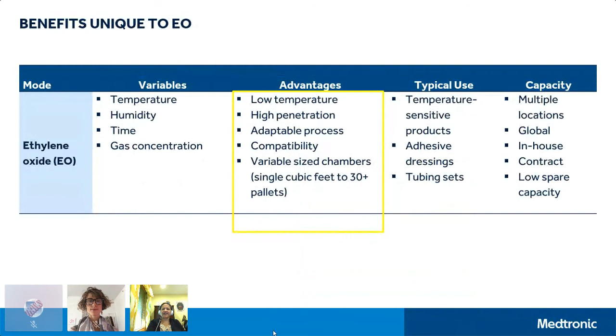One of the things I would like to point out here is a typical sterilization process profile that describes the mechanism of how EO is working. The first step is the preconditioning phase, where you require the load to be brought up to a specific temperature and humidity level. And these are very essential for proper sterilization. The important thing to note here is the humidity requirements. A 30 to 80% humidity range is preferred for optimum sterilization effectiveness.